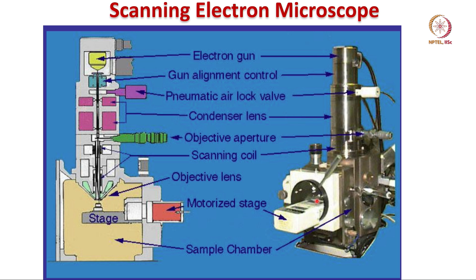Along the path of this electron beam, you have a condenser lens, an objective lens, and so on. These lenses are magnetic in nature, so they are magnetic lenses. It is not like the simple lenses used in the optical microscope. And then there is a motorized stage. This motorized stage is used to control the sample movement. You can do mostly X, Y, and Z movement. Z movement is restricted because that is the working distance between the objective lens and the sample, which is typically kept at a specific value like 10 millimeter and so on.